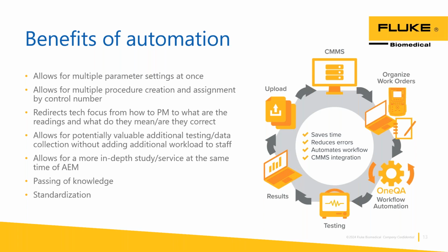So by creating these procedures in a controlled environment where you can sit down with that senior level technician and go through, you might be able to build a procedure that's going to do all the same tests in the manual, but with fewer steps, because now you can check the baseline for ECG and SpO2 and NIBP and IBP, all of those baselines at one time, and then toggle control and then test all the high alarm limits and all the low alarm limits.